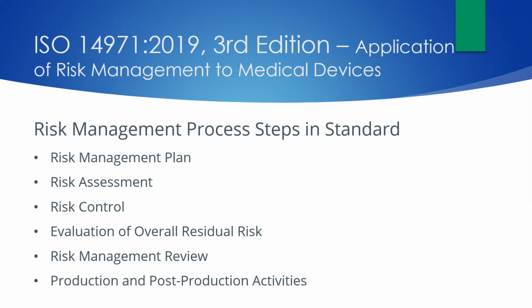Production and post-production activities. There are 4 steps that should be included in these activities. The establishment of systems to collect and review information from production and post-market activities. The collection of relevant information for the device. The review of the information to determine relevance to device safety. And finally, implementation actions. And these can be done by reviewing the risk management file to determine if new risks or previously identified risks need to be assessed or reassessed. So as you can see, an ongoing theme is not only to do these steps, but then to make sure that you're going back and reassessing, revising documents, updating documents, to continue to show that you are managing risk.